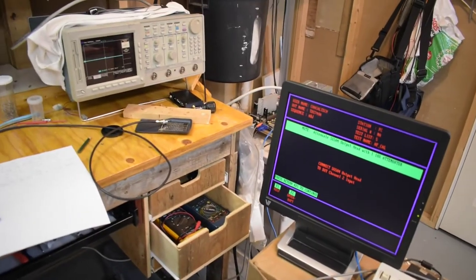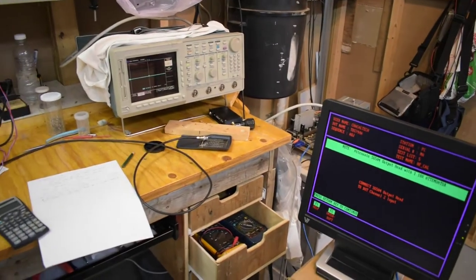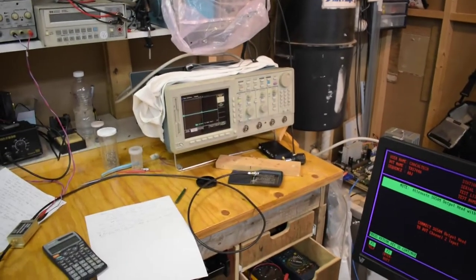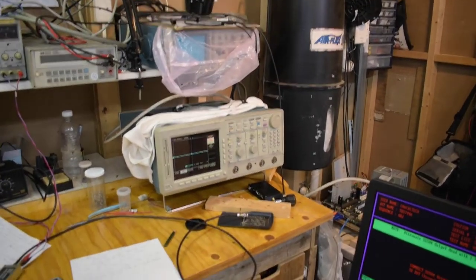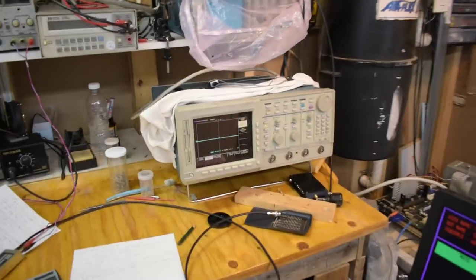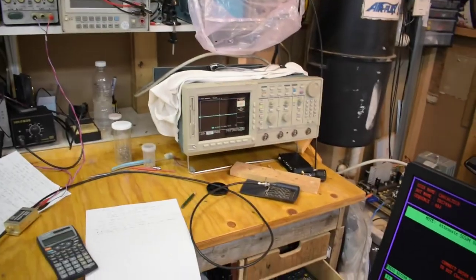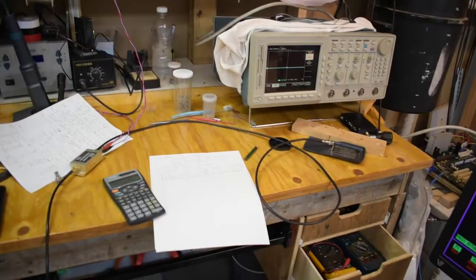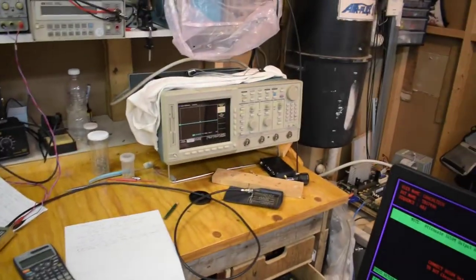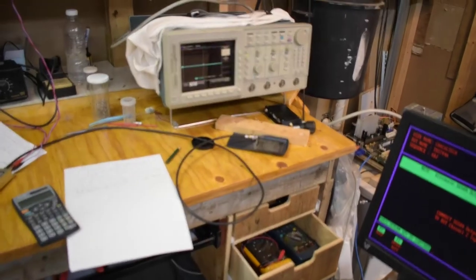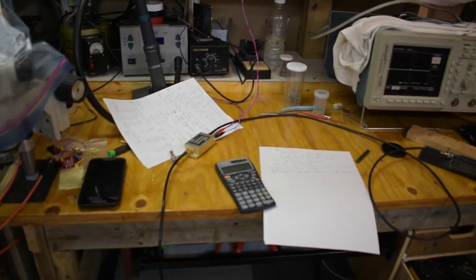Well, interesting. I finished the channel 1 part of the HF calibration. The really problematic ranges were the first ones, where it's like 1 millivolt per div. And I think I got a better plan for channel 2 now. The first few ranges I'll do with a 20 dB attenuator without the amplifier.